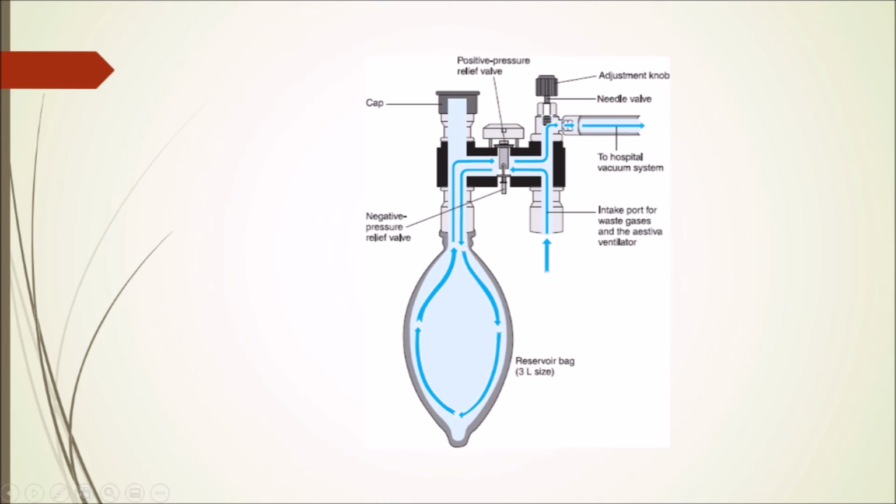Since the amount of anesthetic gas supplied usually far exceeds the amount necessary for the patient, pollution is decreased by scavenging. Scavenging and operating room ventilation efficiency are the two most important factors in the reduction of waste anesthetic gases.